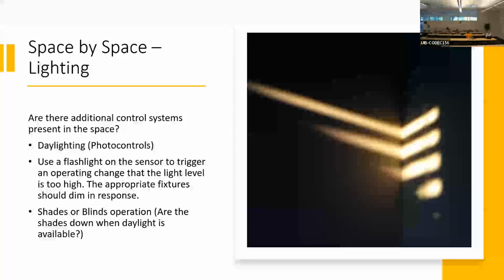Are there additional control systems present, like daylighting? If so, and you want to test the photo control, shine a flashlight on the sensor—that tells it lumens have increased dramatically and it should reduce electric lighting. If it doesn't respond, something's wrong.